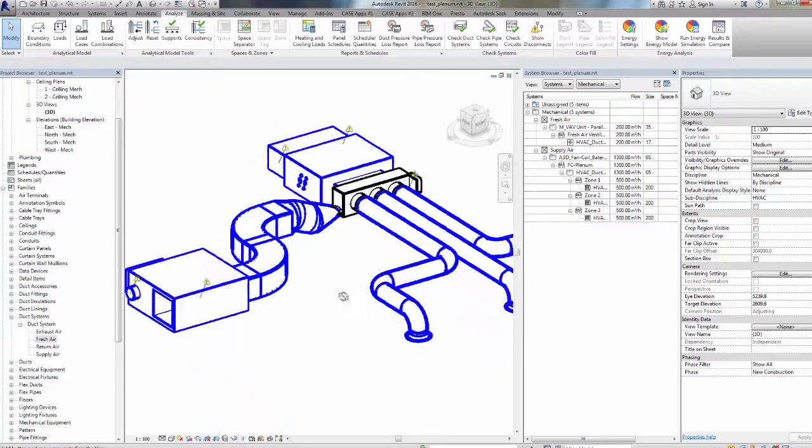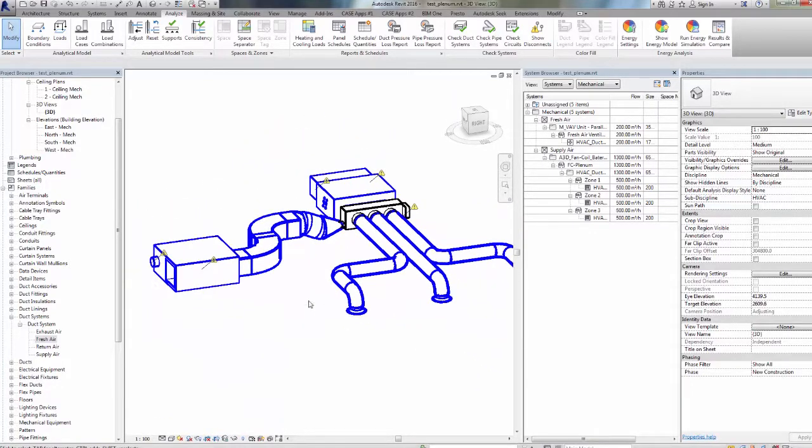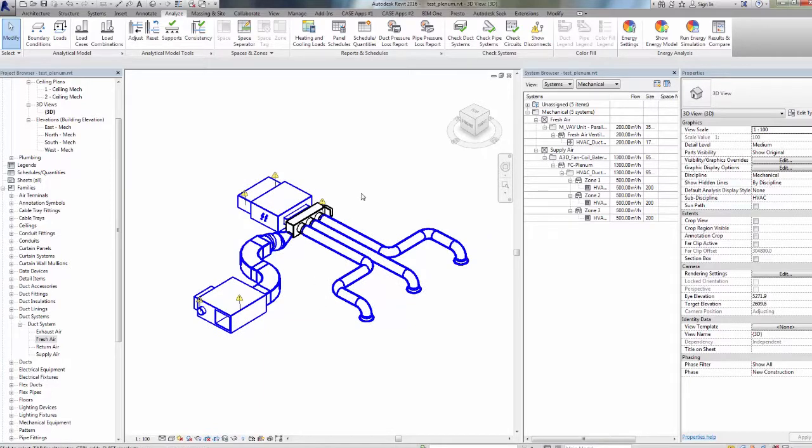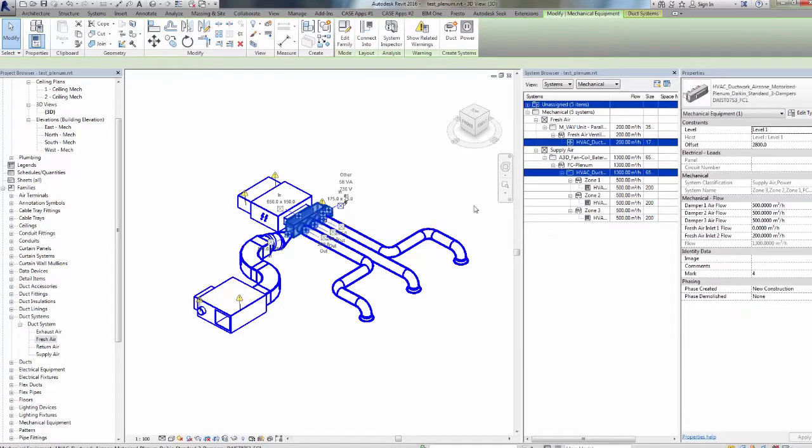And here, the whole model can be observed. We see how the plenum includes the airflow values from the outlets and the fresh air airflow. We see that the indoor unit is making right calculations and that all of them appear on the system's browser.